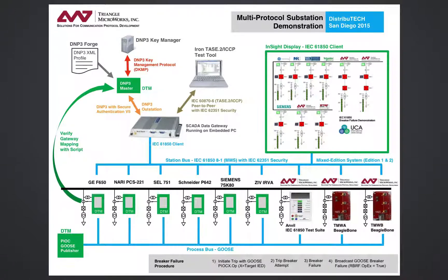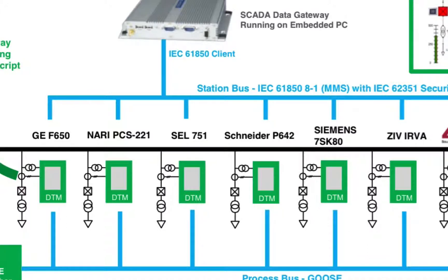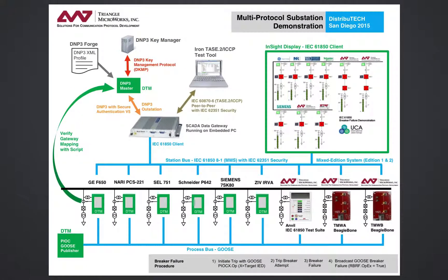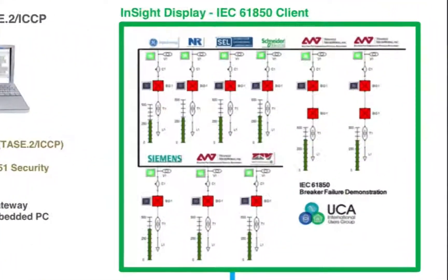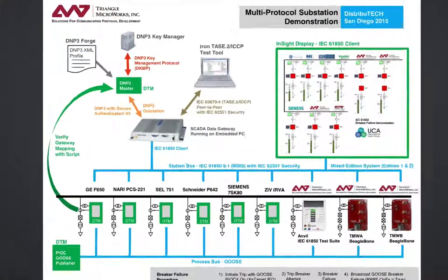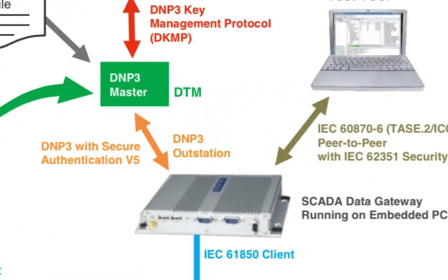In this demo, DTM simulates 6 IEC-61850 servers defined in the substation SCD file. In addition, we're using DTM as an IEC-61850 client to monitor the network status directly, and as a DNP3 master obtaining data from the IEDs through the SCADA data gateway.